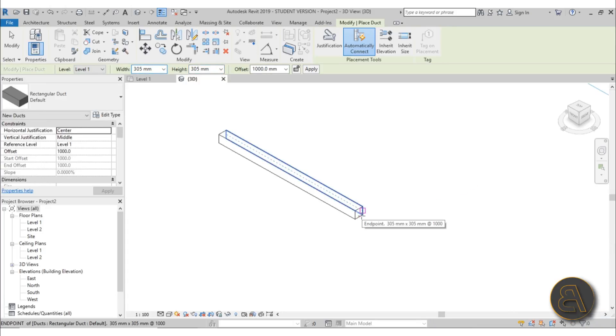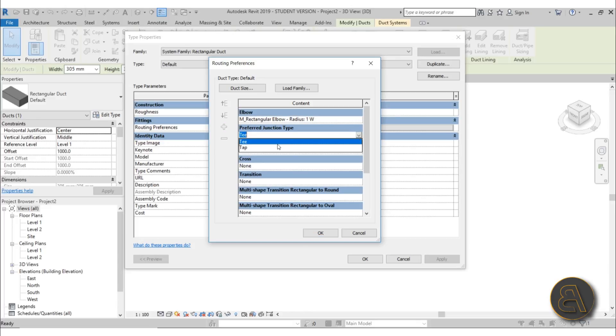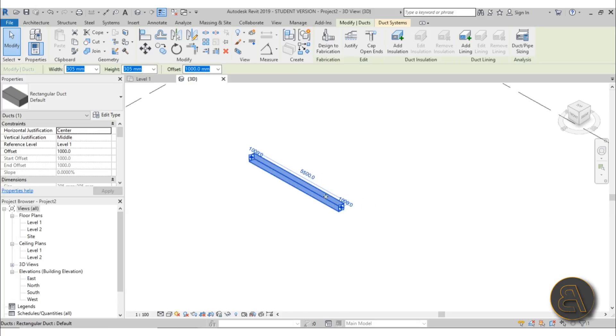Those families are loaded in, but they're not yet associated to the rectangular duct. To associate them, go to Edit Type for the duct, then find Routing Preferences. Here you can assign all of the duct fittings you loaded. For the elbow, assign the rectangular elbow with a radius of 1, 1.5, or 2 — let's go with the smallest. Assign fittings for taps and the other types as well. Click OK and apply, and now the duct tool works — we can finally create ducting in the Revit architectural template.